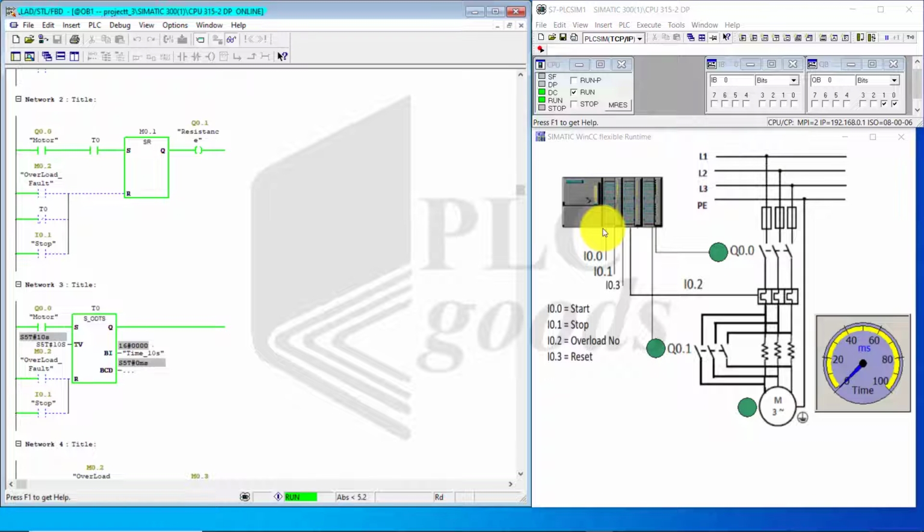Okay, friends, in project number 3, it is starting a squirrel cage three-phase motor with initialization resistors. Develop a PLC control program based on the following condition. Case 1. When the start or I0.0 push button is depressed, the three-phase motor starts by the presence of initialization resistors in series with the power supply to the motor.